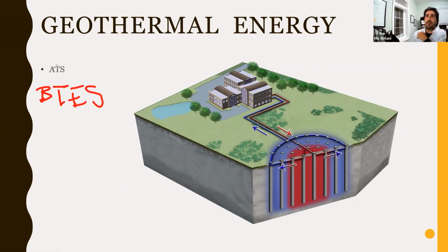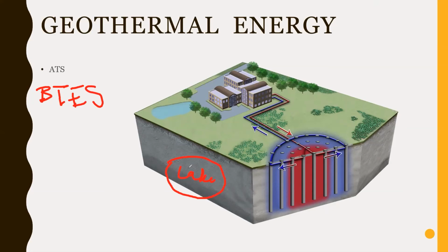So Peter, regarding ATS, you said there should be a lake underneath. Correct, you pump from one end. Is it hot or cold, how cold is that lake? Usually about 45 to 50 degrees. And you could say this is the lake here; usually the line that goes into it is about a 10-inch line, and you can pump a system good for about 300 to 400 tons.